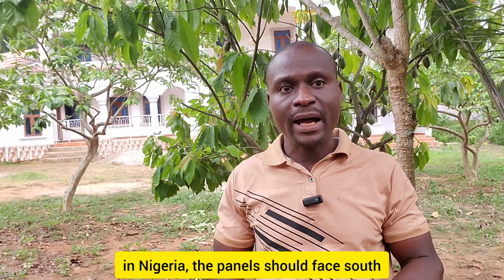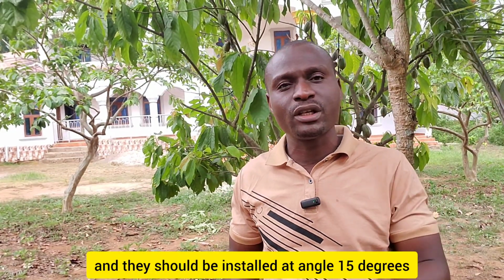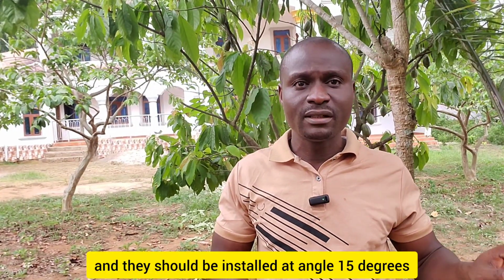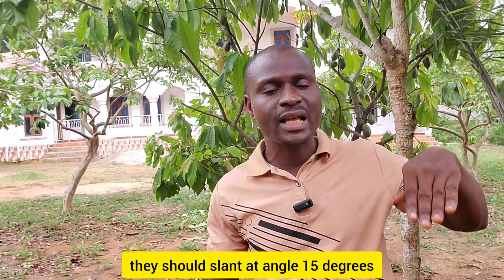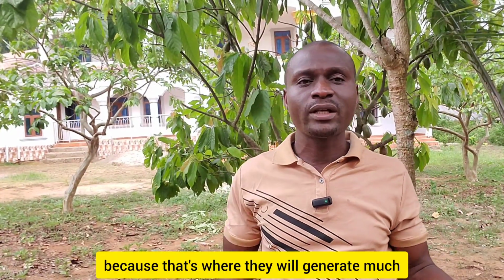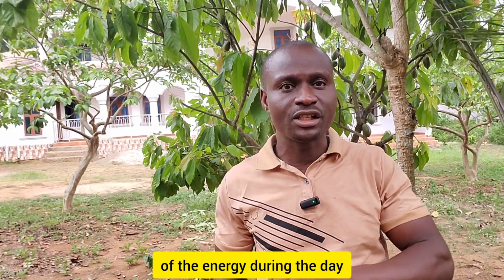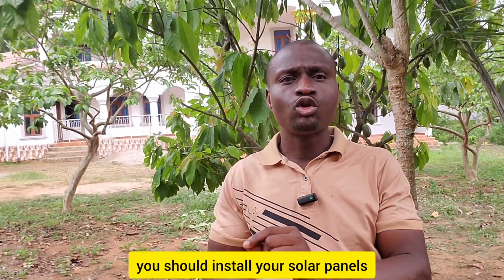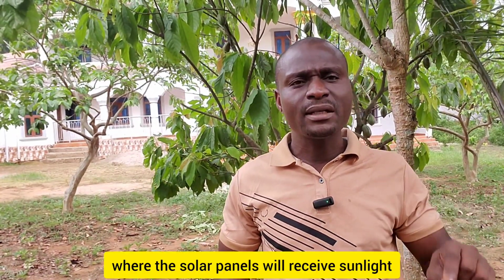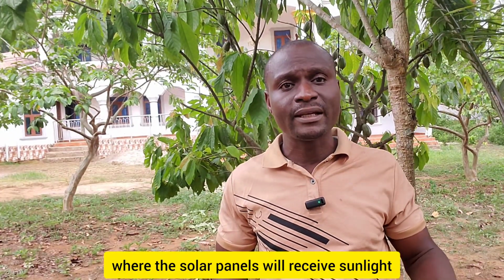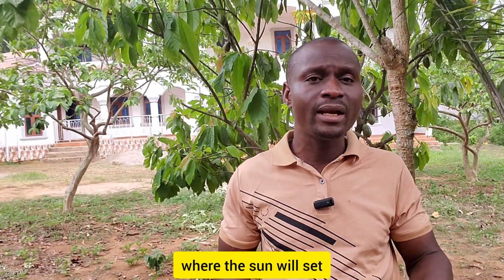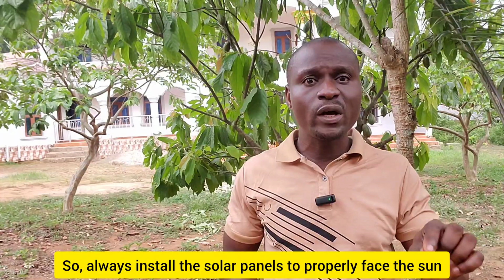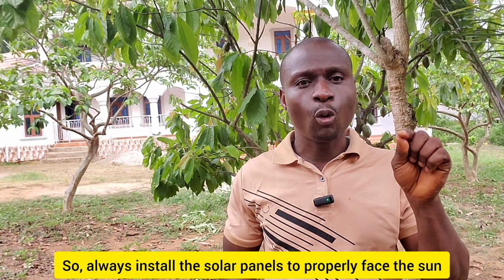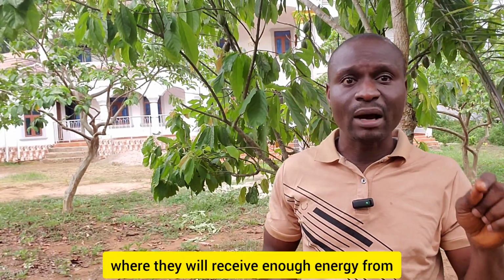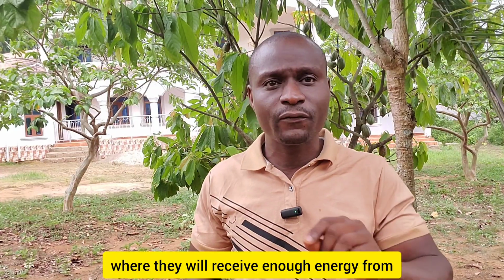In Nigeria, the panels should face south and they should be installed at an angle of 15 degrees. That is, they should slant at an angle of 15 degrees and face south because that's where they will generate much of the energy during the day. In other words, you should install your solar panels where they will receive sunlight from morning till evening, where the sun will set. So always install the solar panels to properly face the sun where they will receive enough energy from morning till evening.